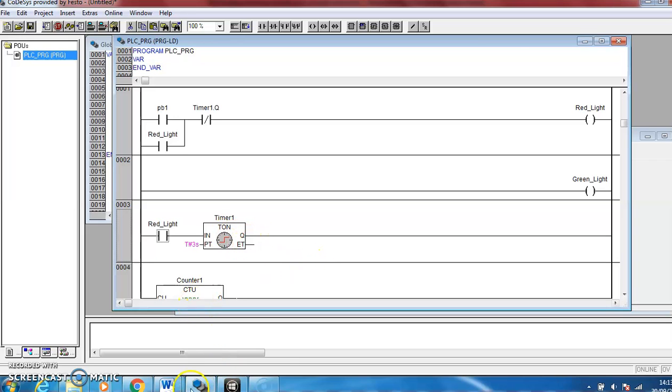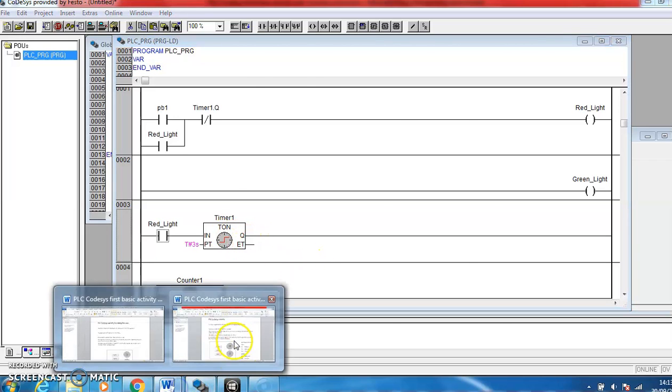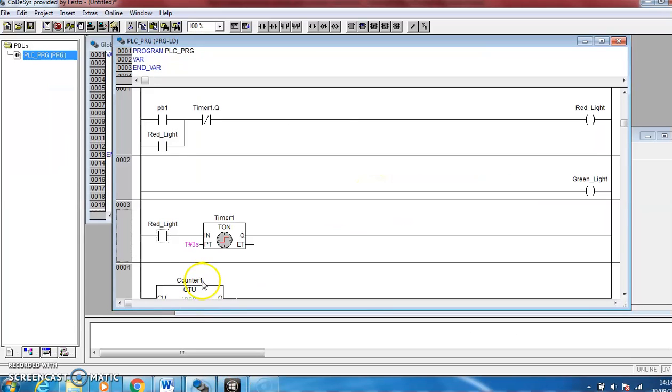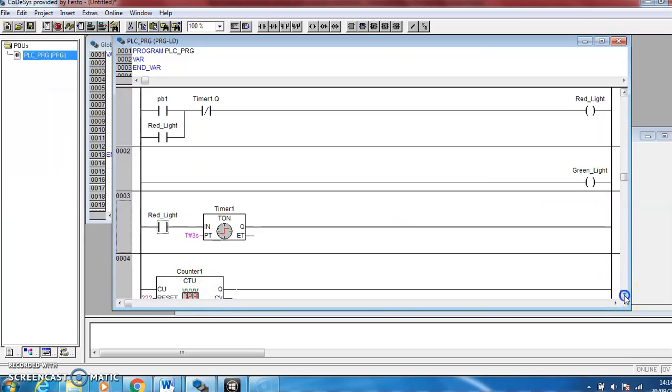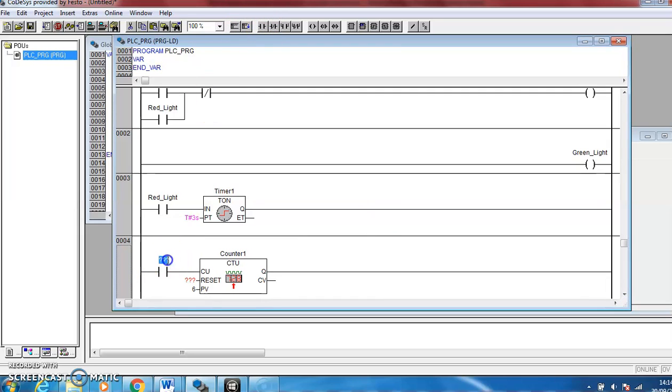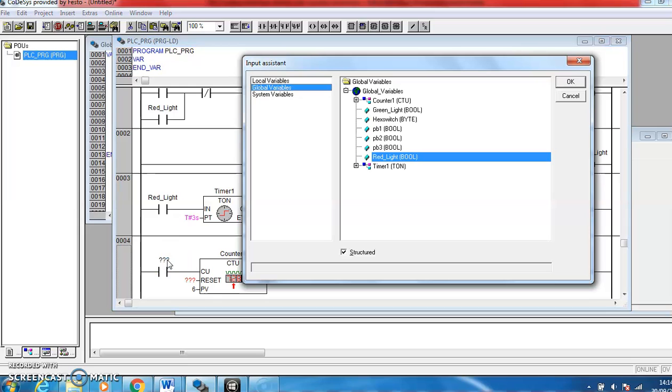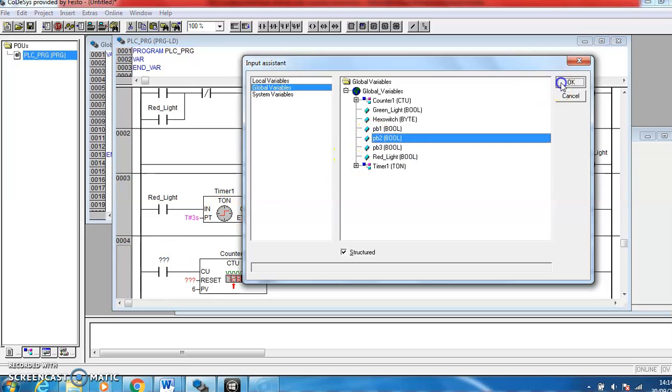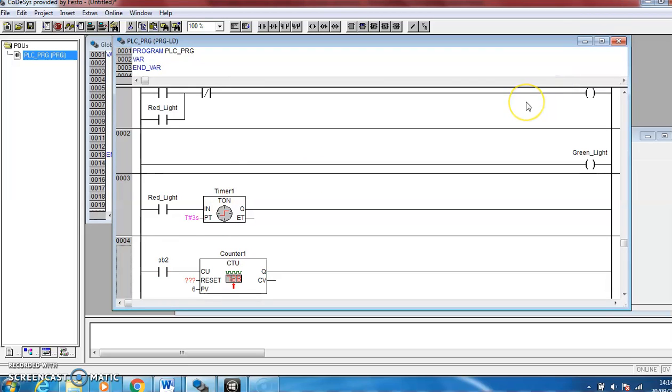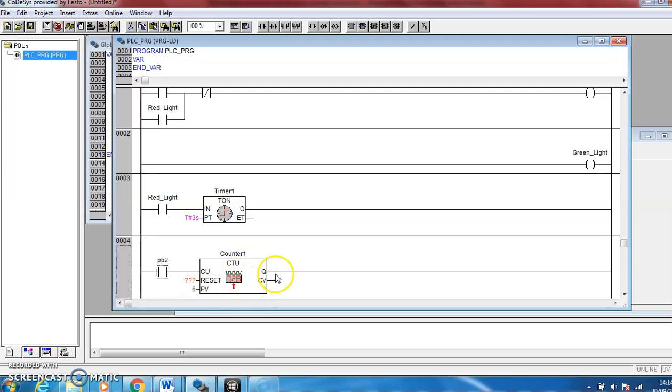So back and read our little diagram again. When push button 2 is pressed six times, the green light will come on. So back to our program, we need this counter to get a signal from push button 2. So now every time the push button gets pressed, the counter will count up one. Once it gets to six, it'll turn on this Q value. Once that Q value is on, it needs to turn on the green light.